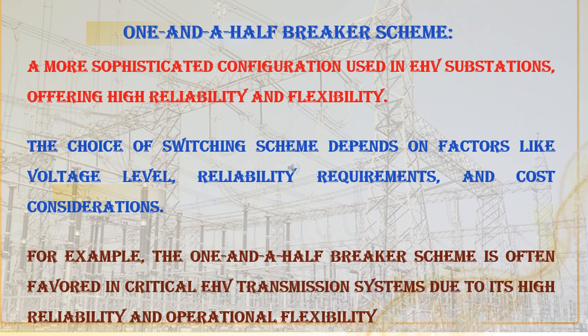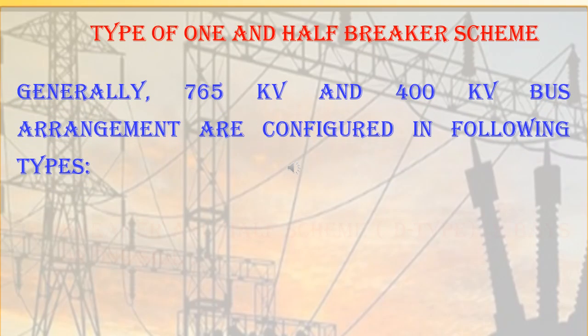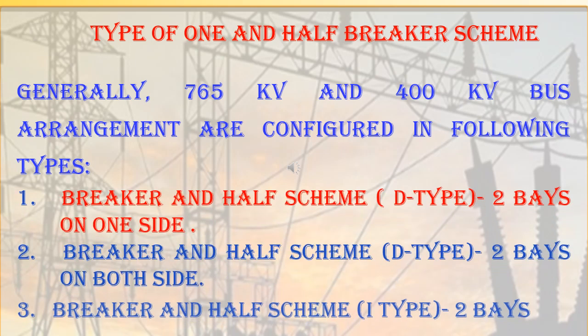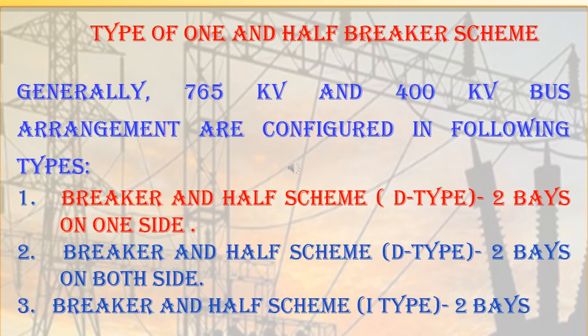and operational flexibility. The 1.5 breaker scheme is very common in 400 kV schemes. The 1.5 breaker scheme is very popular in 400 kV substations and 765 kV substations. In 400 kV substations, generally D-type 2-bay one side or D-type 2-bay both side and I-type schemes are used. In 765 kV substations, generally the I-type 2-bay scheme is used.